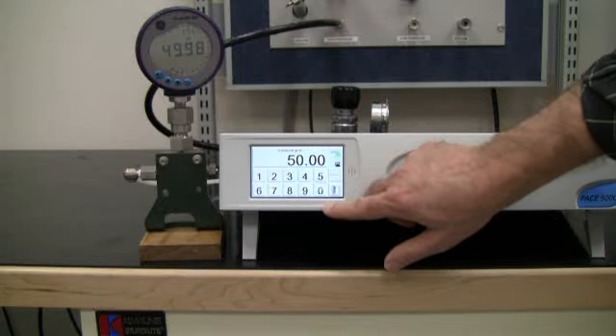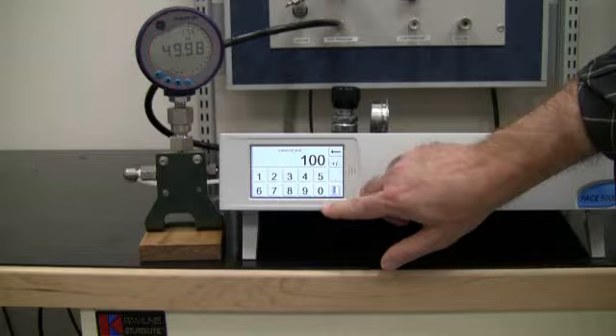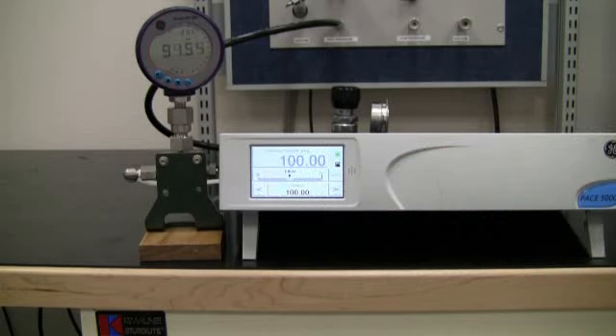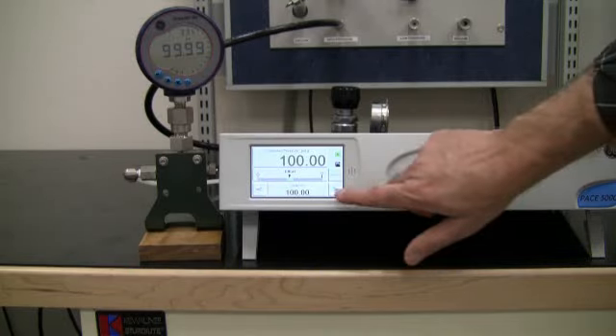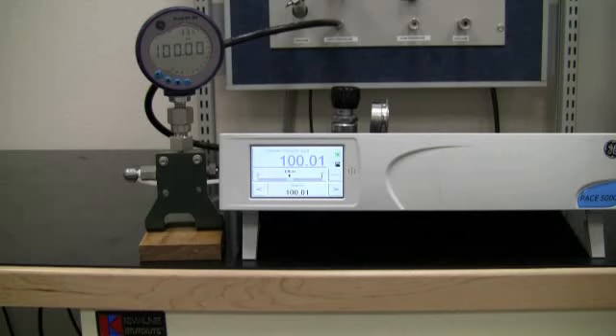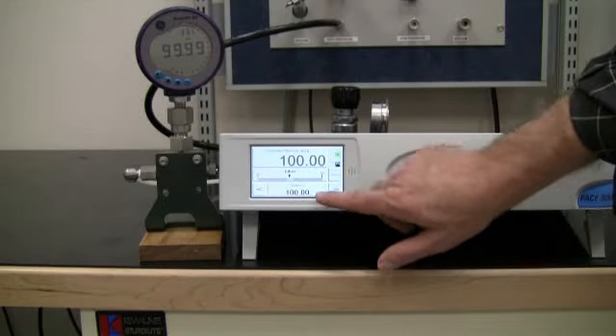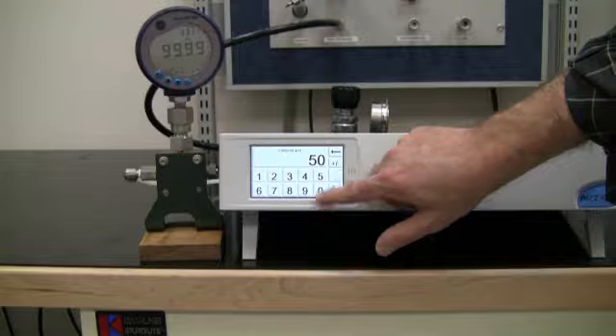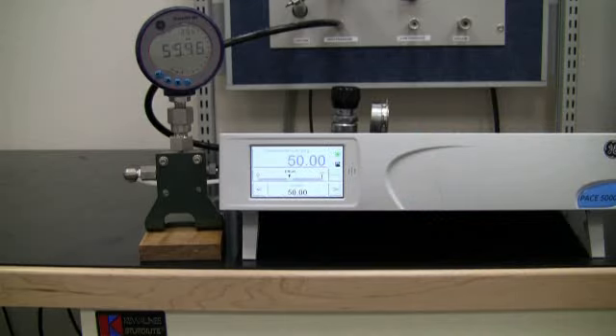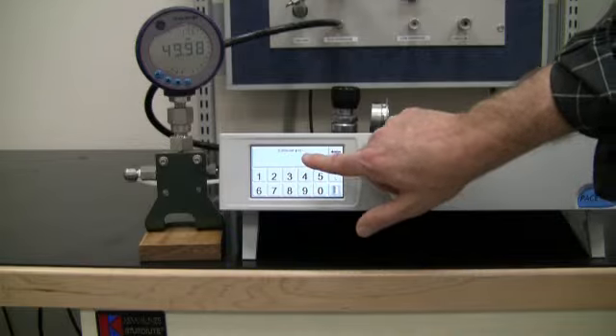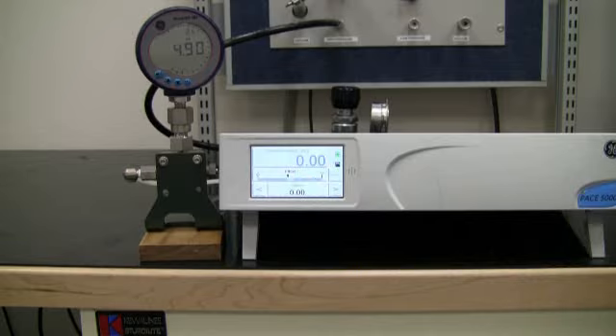Our next set point is 100 psi. Again, notice how fast the controller achieves the set point and the pressure reading changes from blue to green. We can nudge up to achieve a cardinal pressure reading on the DPI 104. We will now control back to 50 psi. PACE5000 is so fast, we have to wait for the device under test to catch up. Next, we will control to 0 psi. We will then change from control mode back to measure mode and select the vent function.